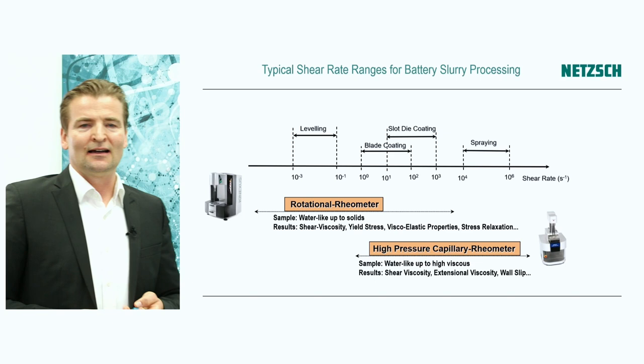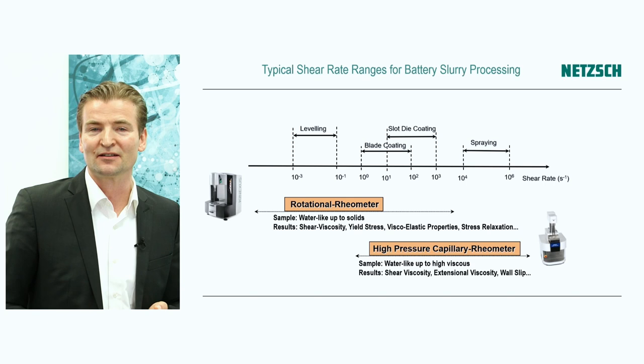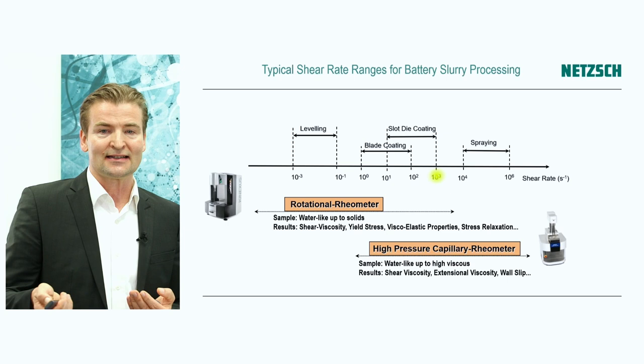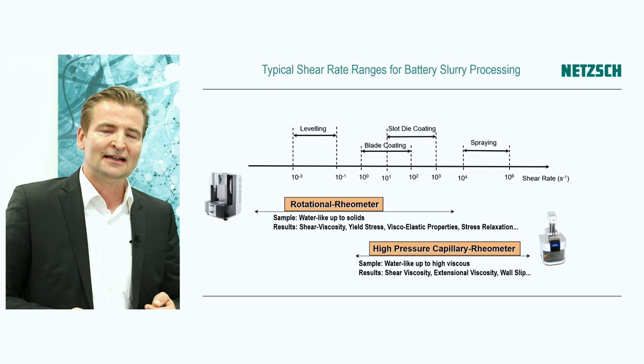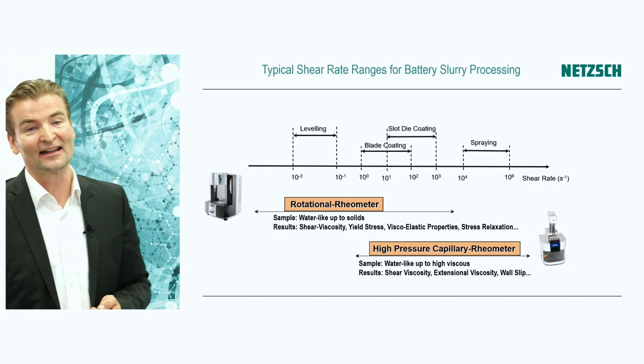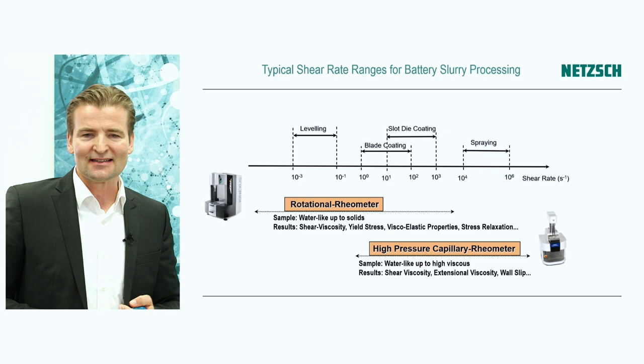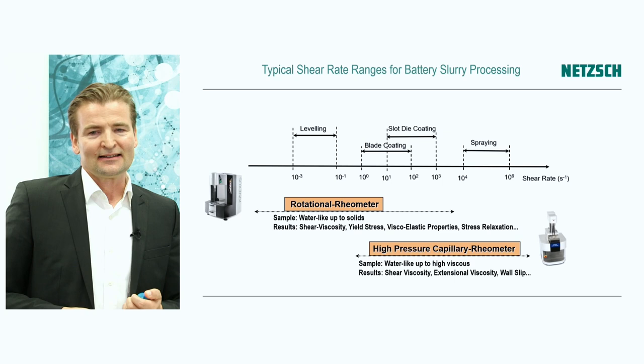When you calculate those terms for blade coating, you end up with shear rates typically in the mid range, around 1 to 100 reciprocal seconds. Slot die coating is typically a bit faster, with shear rates from 10 to about 1,000 reciprocal seconds. Spray coating is in the high shear rate region — between 10⁴ and 10⁶ reciprocal seconds. This wide shear rate range cannot be covered by a single rheometer. Our rotational rheometer, the Kinexus, covers the low to mid shear rate range, including leveling behavior. Our high-pressure capillary rheometer, the RH2000, covers the mid to high shear rate region. For spray coating, a capillary rheometer is definitely needed.